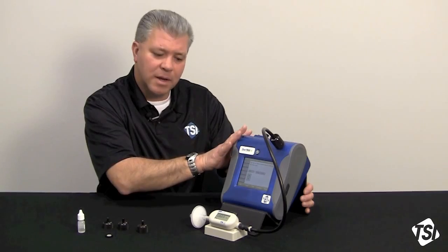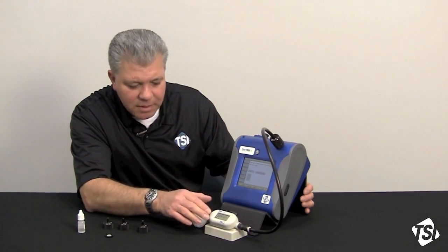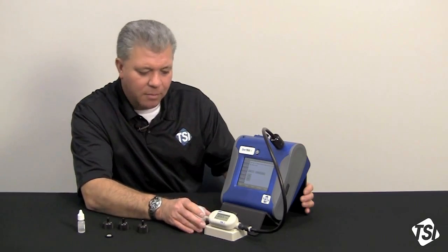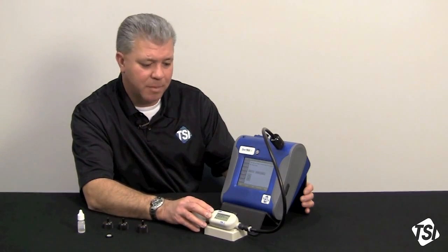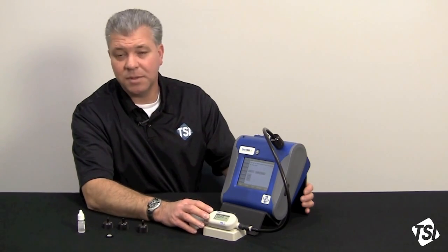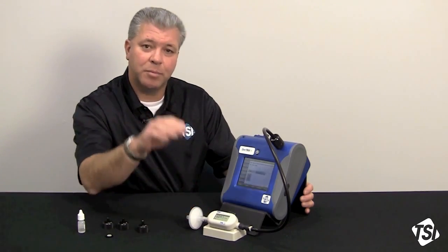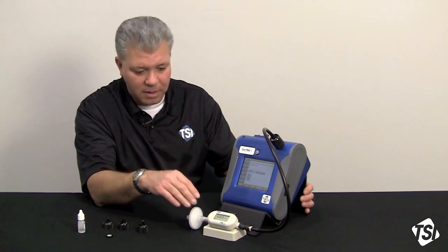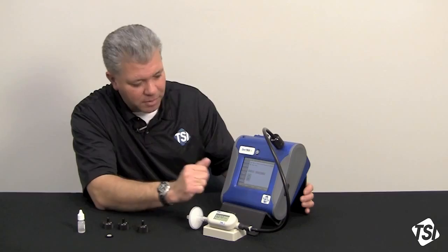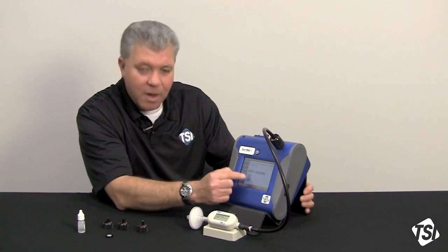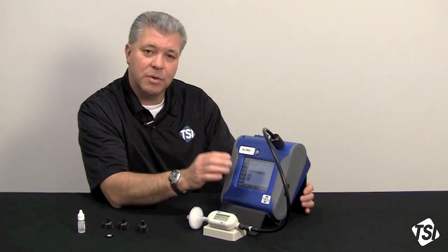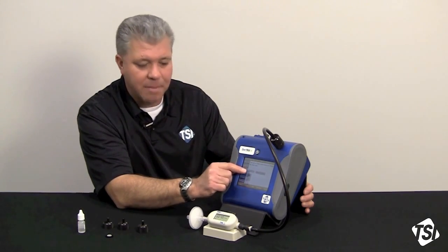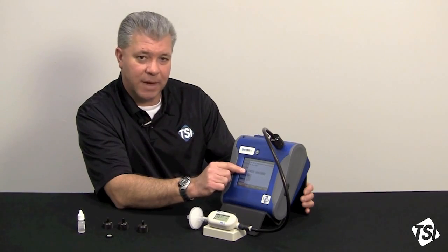The pump is going to start running in the DustTrak, and I'm immediately going to see a flow rate shown on the calibrator. And the real nice thing about these 4146 primary calibrators is that they're real time, just like the instrument. I don't necessarily have to prime a bubble burette with a soap bubble for a couple of minutes to get it primed and ready to go. I'm immediately taking data, I'm looking at the flow rate, and what I want to advise everybody about a DustTrak 2 and the DRX is that you're going to see a span potentiometer range shown on the instrument's face.